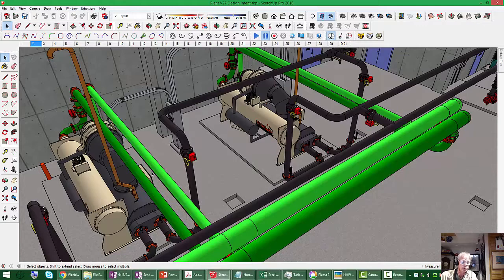But the chillers aren't identical, and so what that implies is if the chillers aren't identical, there's probably a reason they're different. There's probably one chiller that's intended to carry the load swings and low load conditions, and another chiller that's intended to be a peaking machine. So that would suggest that both chillers are intended to be in operation when the plant is at full load, versus one chiller being a redundant chiller for the other chiller.